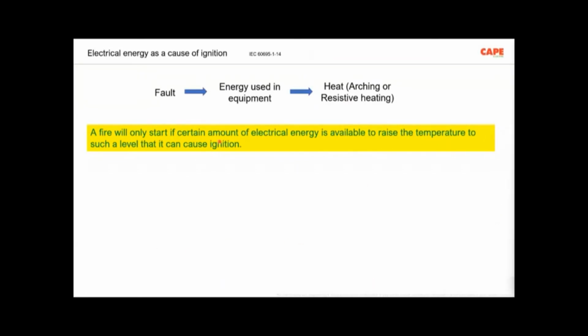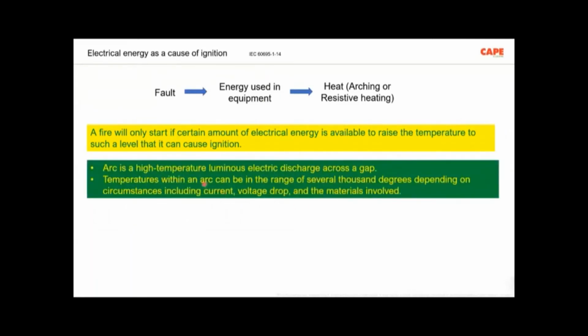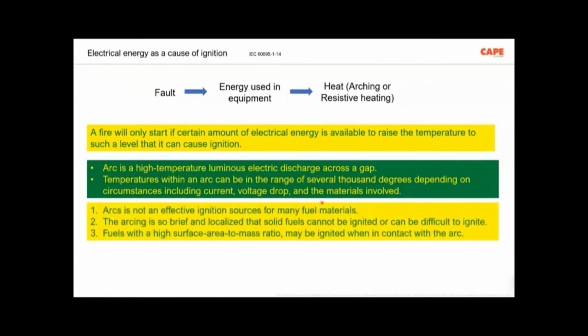Thank you, sir. So now, electrical energy causing fire. The IEC 60695-1. One misinterpretation which I wanted to tell you about is arc, whether arc can ignite fire. Arc is a high temperature luminous electrical discharge across a gap. Temperature within the arc can go to several thousands of degrees, but arc is not an effective ignition source for many fuel materials. Even for solid combustible materials, arc cannot ignite because it is for a very short time.